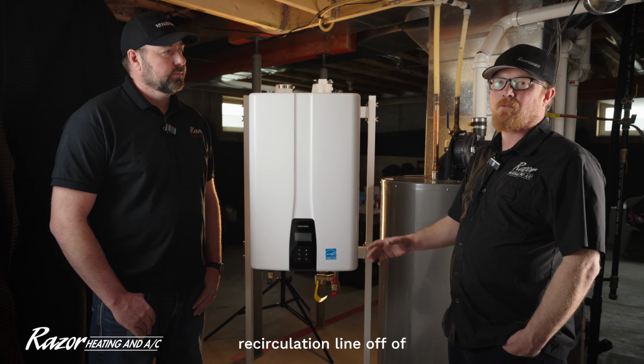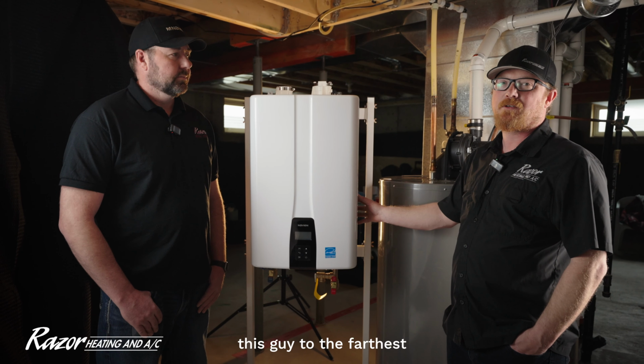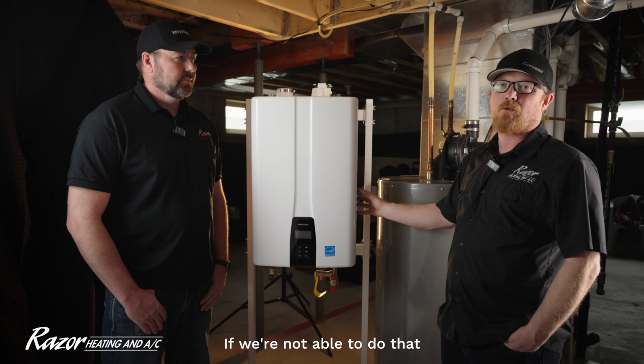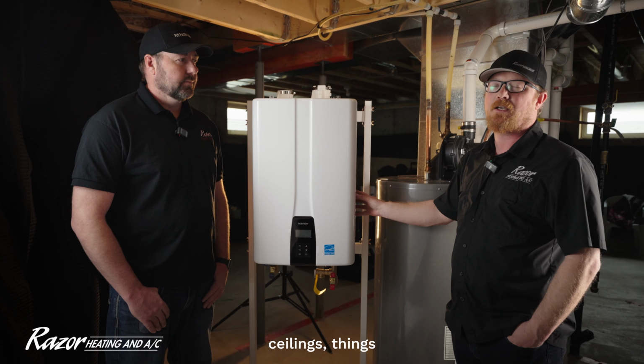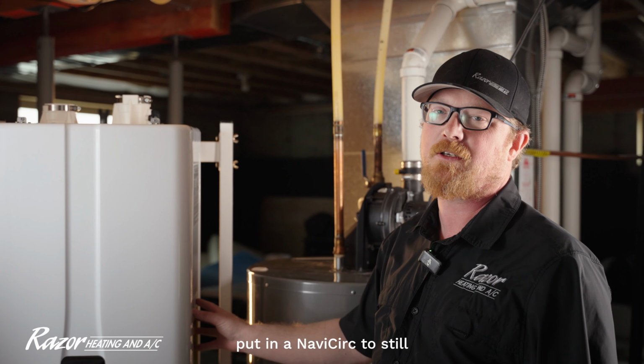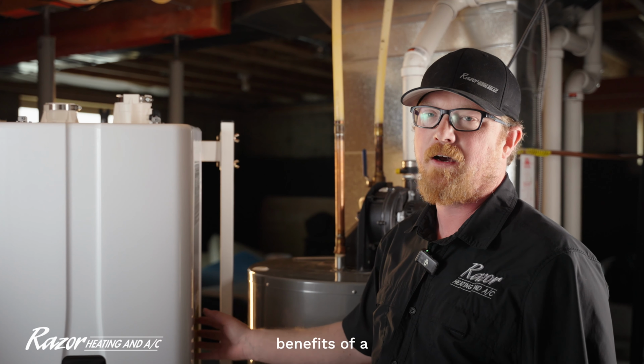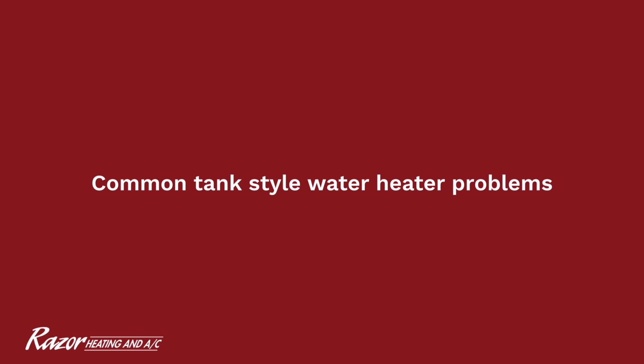We'll either run a recirculation line off of this guy to the farthest fixture if it's capable. If we're not able to do that because of drywalled ceilings, things like that, we can put in a NaviCirc to still give you the recirculation benefits of a tankless water heater.